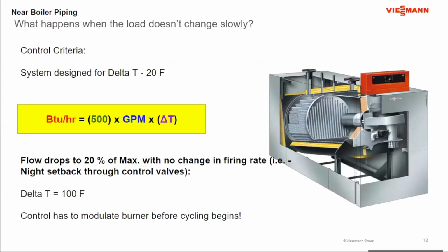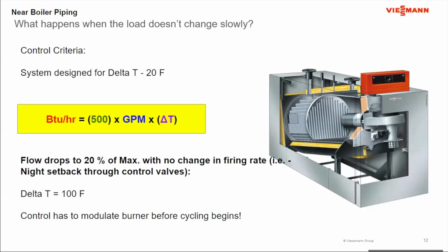Now, everything is well and good when things happen slowly. We're able to measure the temperature, allow the time to accumulate, and then make the adjustments, and the boiler modulates, and there's not a lot of cycling, and nothing touches the limits. Things operate a little bit differently when we start to change the load quickly.